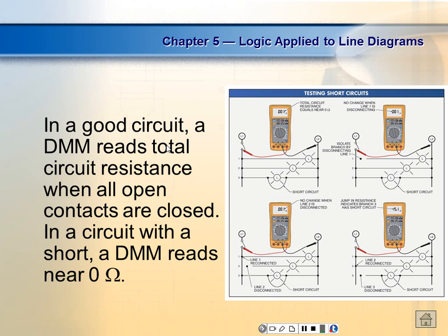Well, it depends on what it is. So y'all were running a grounded L2. So when you hooked it to the cabinet, that was actually L2. So that's good. Where I see it says it's near zero, well, you don't have a short. What you have is a resistance that's not supposed to be there. Does that make sense? So those were not really shorted. To be shorted, they would have kicked something, right? They would have kicked the overload. They'd be kicking the drives upstairs.